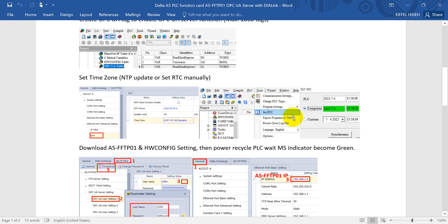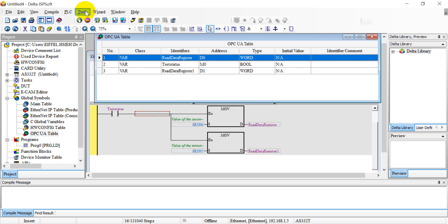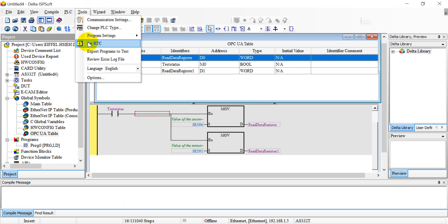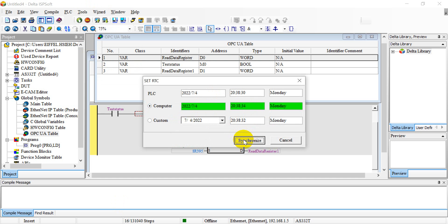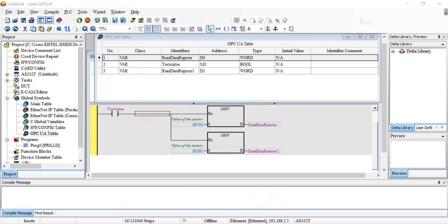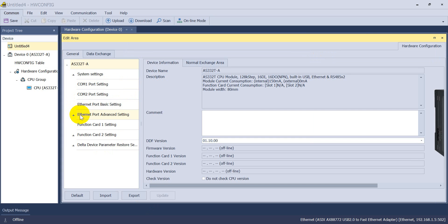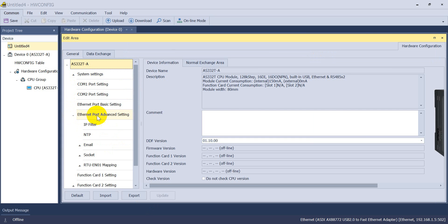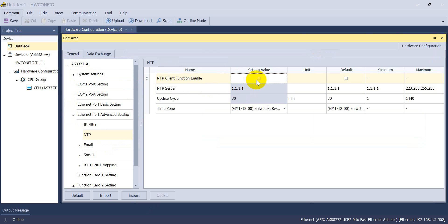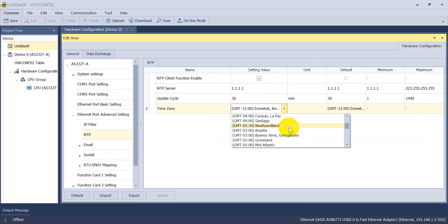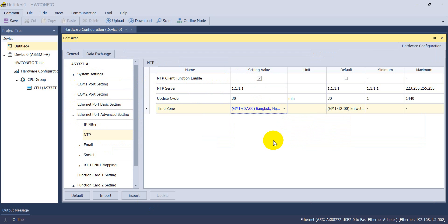Today I will show you the real-time clock synchronization with the PLC and laptop. You can see here — select Tool and Set RTC, then click Synchronization. If you want to use the NTP server, go to Ethernet port advanced settings for NTP, enable it, type in the NTP server address, and select the time zone for your country. Then download the settings.